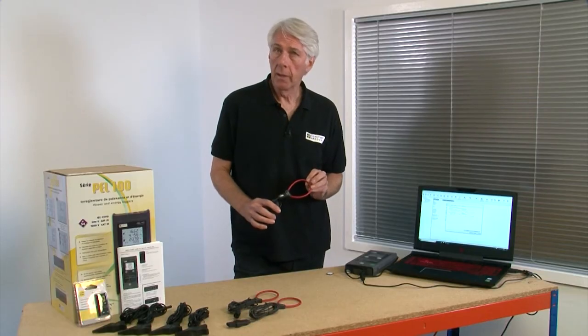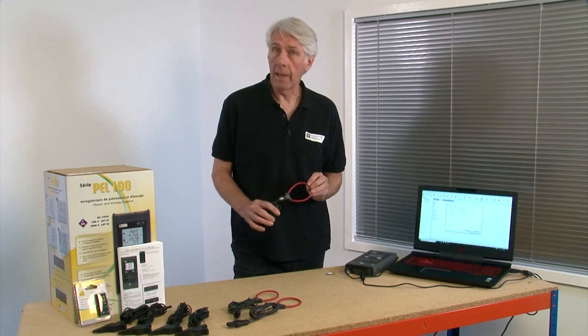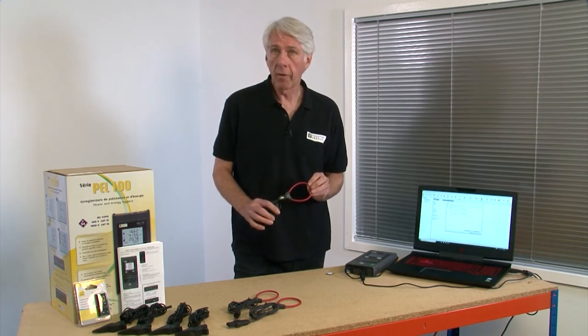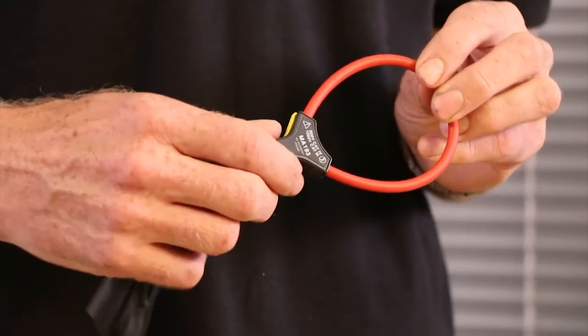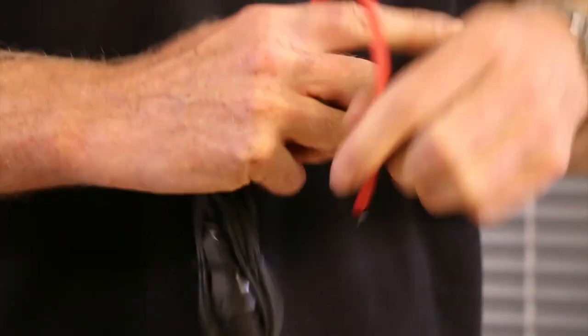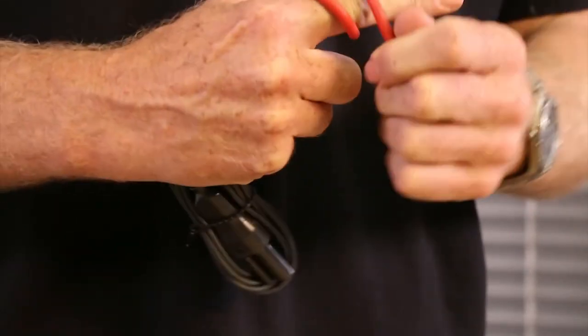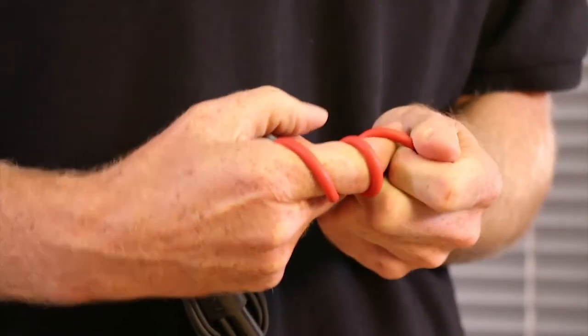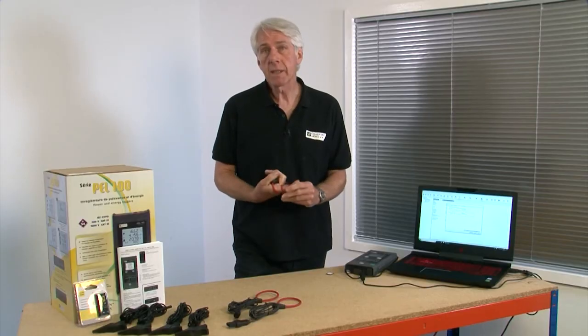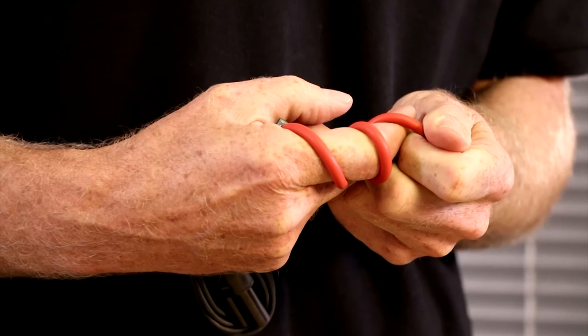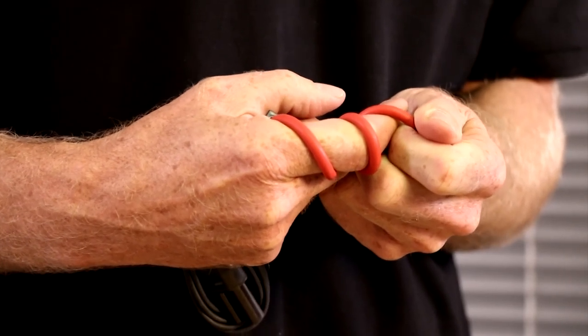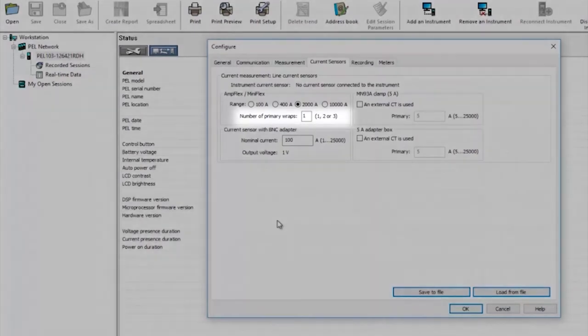As standard the PEL comes with three mini flex Rogowski coils. It'll measure anything from 100 milliamps to 10,000 amps and so will suit a very wide range of applications. If you're measuring very low currents you can wrap the Rogowski coils around the conductors a maximum of three times to increase the sensitivity and if you do simply select the number of wraps here so that the PEL knows and will adjust the measurements automatically.